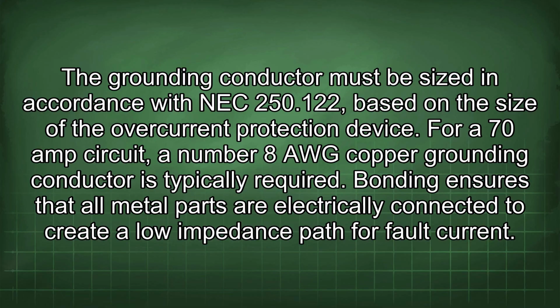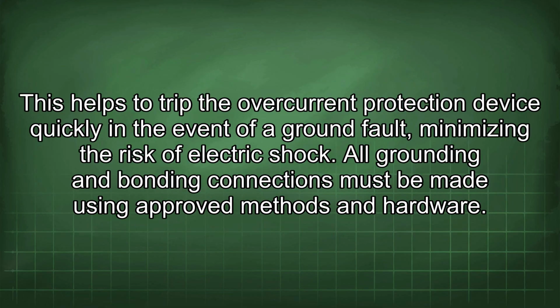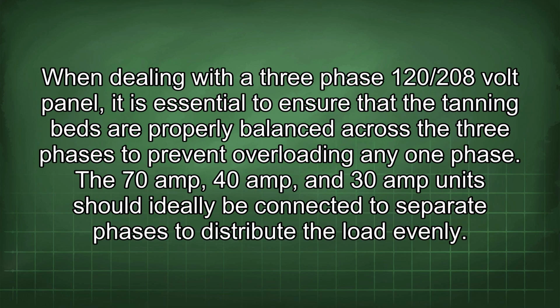Bonding ensures that all metal parts are electrically connected to create a low impedance path for fault current. This helps to trip the overcurrent protection device quickly in the event of a ground fault, minimizing the risk of electric shock. All grounding and bonding connections must be made using approved methods and hardware. When dealing with a 3-phase 120/208 volt panel, it is essential to ensure that the tanning beds are properly balanced across the 3 phases to prevent overloading any one phase. The 70 amp, 40 amp, and 30 amp units should ideally be connected to separate phases to distribute the load evenly.